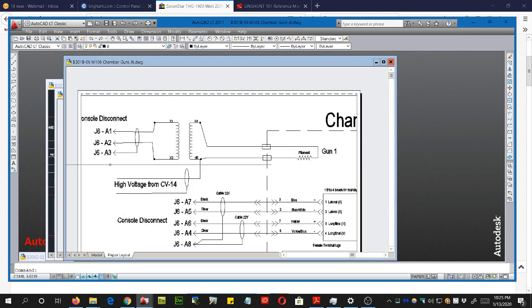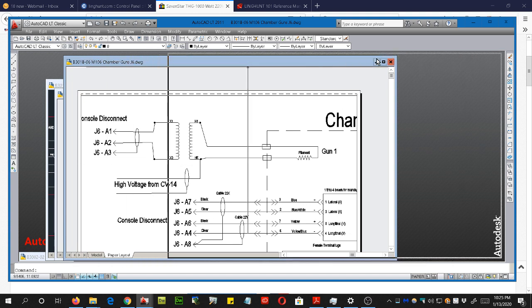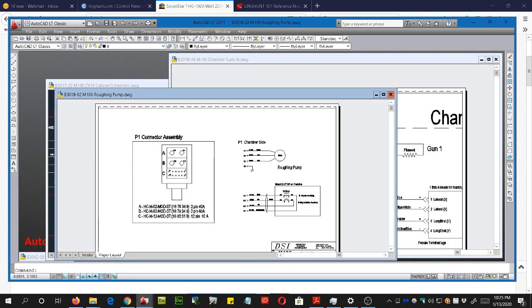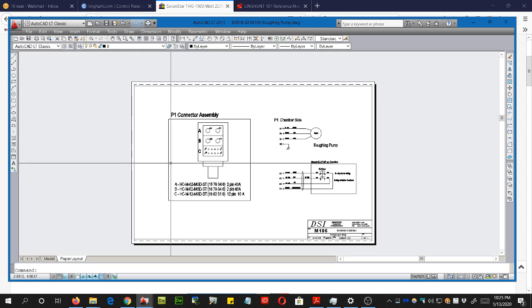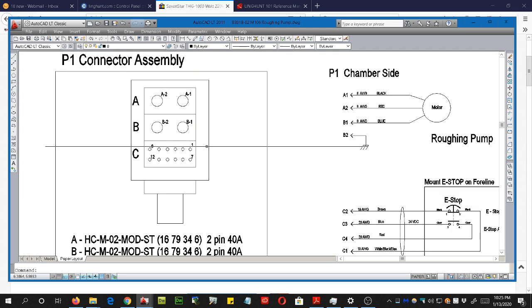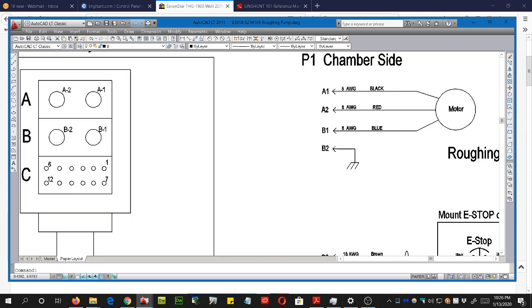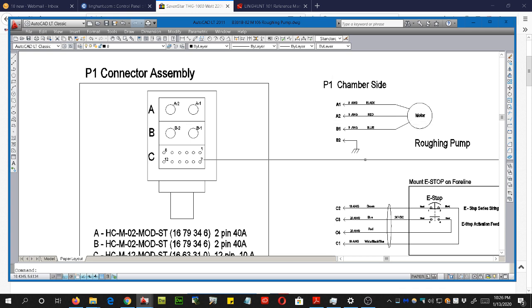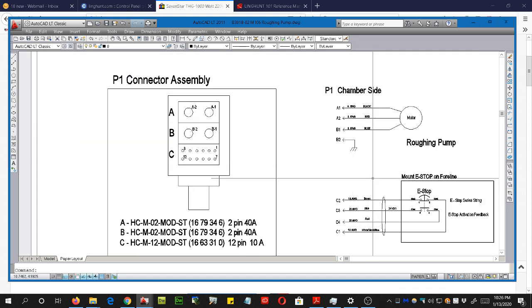Okay, here's a transformer. Actually, I should show you this other one first. Try that one. Actually, we'll do this one. I got a plug that goes out there, and I can build these plugs any way I want. So I got 4 big wires, and I got a bunch of little wires. So here's the motor for the roughing pump, and we saw where that came from on the other sheet. And here I got my black, red, blue again. And here's the 3 phases, and there's the ground. No neutral, not needed. The return path is the other phases, so you don't need to have a neutral. So if you guys look at your welders or your electric oven, you got 3 wires, 2 phases, and a ground. You don't have a neutral.